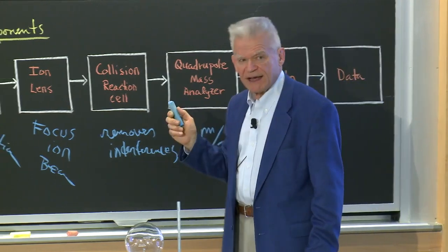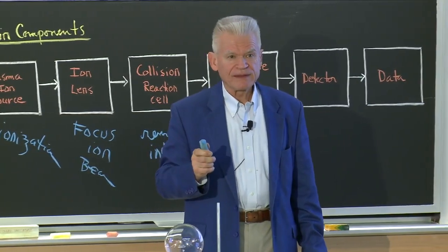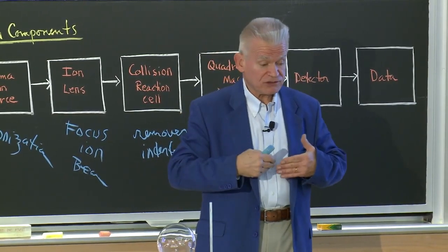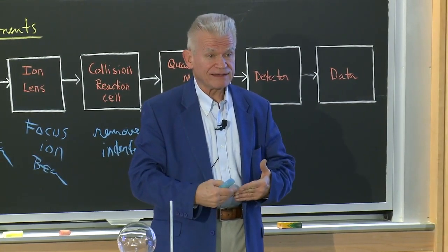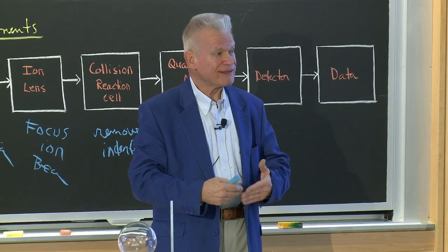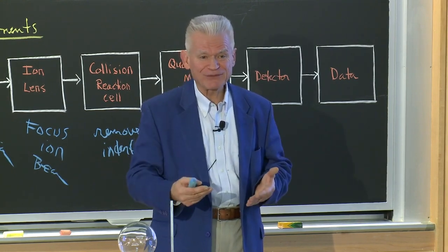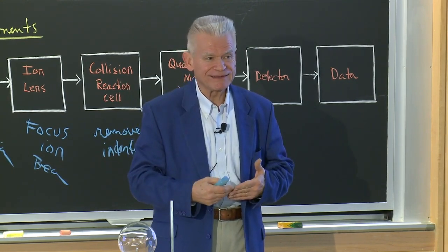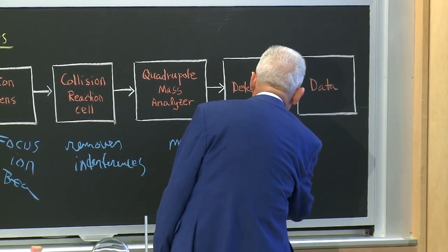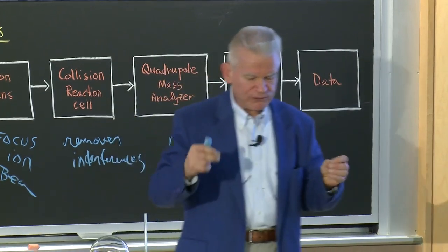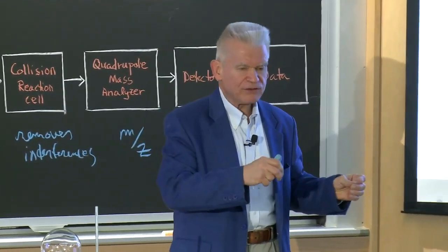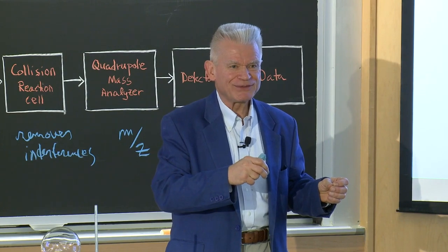The ions are then counted at the detector. The detector actually records the counts per second of every ion hitting it. And these counts can be like hundreds of thousands of counts for each ion every second. So counts per second recorded. And interestingly, the detector takes those counts per second, and then it looks at our calibration standards.